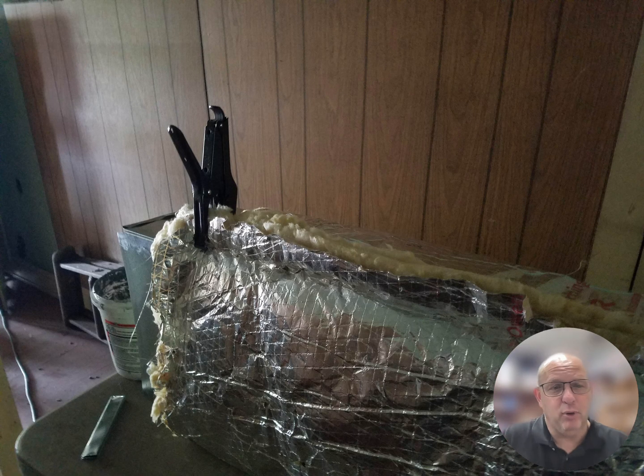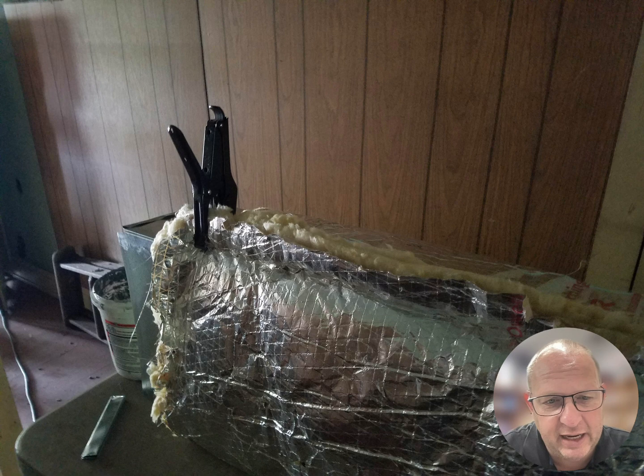Okay, here's a great example. We're going to measure this ductwork, and what I always do is add about 4 inches extra after I've measured all 4 sides of the ductwork itself, for that insulation that's going to be going around the exterior. I'm going to fold it up into a little seam on that ductwork, and I'm going to use my stapler. This is a special stapler for that ductwork, and I'm going to go around the seam, making it nice and tight, but not too tight. Then I'm going to staple that seam all the way down through that system so that everything's nice and tight.